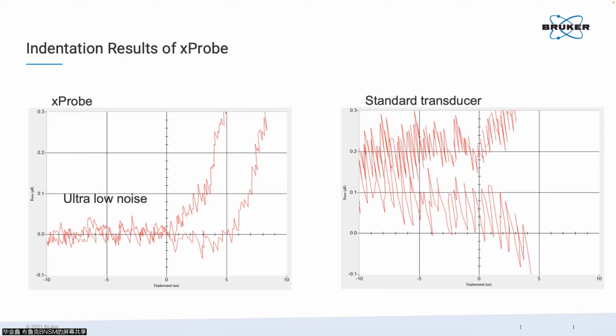So this is the comparison of two transducers. This is the data collected from our standard transducer, and on the left hand side is the data coming from an XP. You can see the y-axis is the force with exactly the same range. You can see this is the noise for a standard transducer, which is much larger than XP. That is the key reason that we are able to make a very shallow indentation, and it is the key point for characterization of the intrinsic mechanical properties of an ultra thin film.